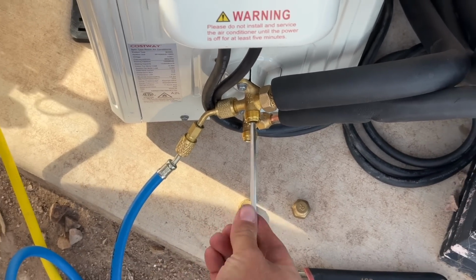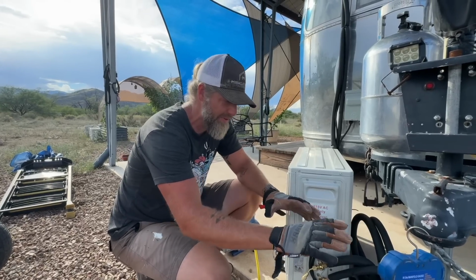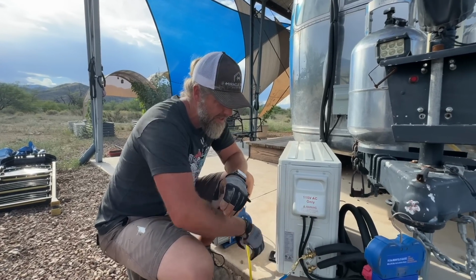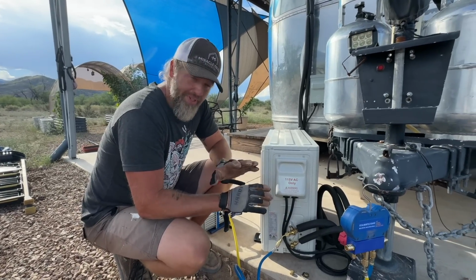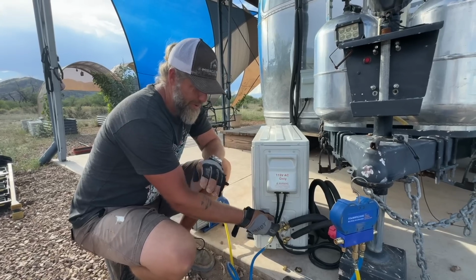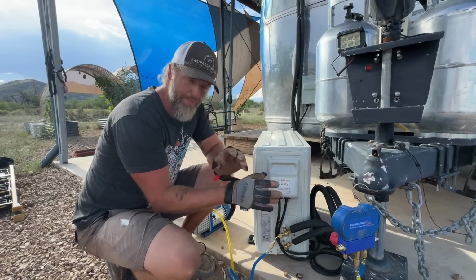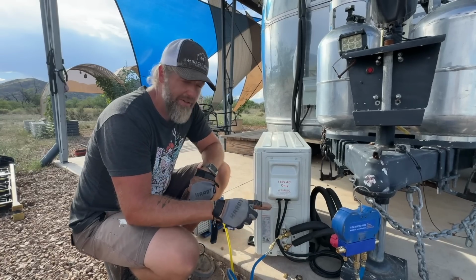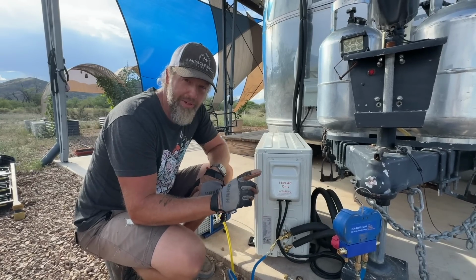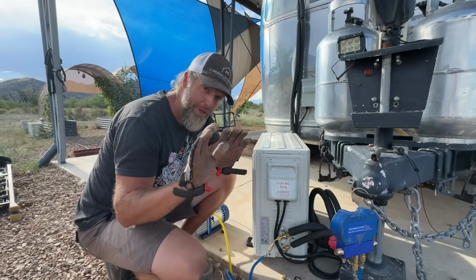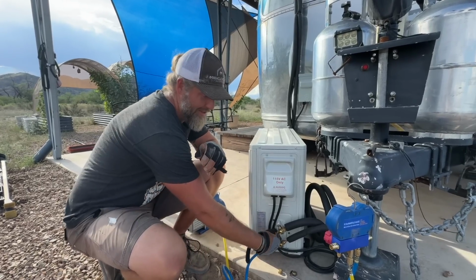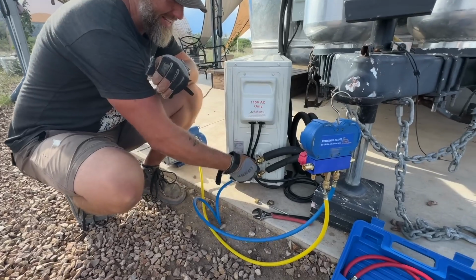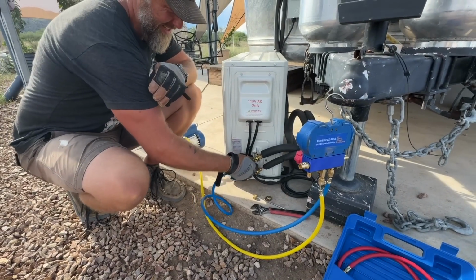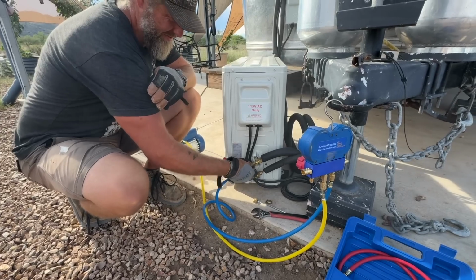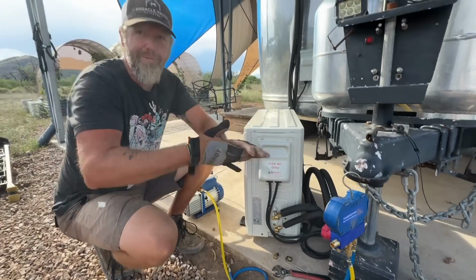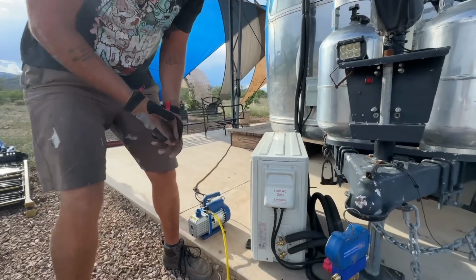Now here's the last thing: we have to disconnect the whole manifold off of this service port. There's refrigerant in there, and since this is a Schrader valve, it's going to want to spray refrigerant when you do this. Your instinct will be to stop when you hear it - don't, just keep going, wear gloves, and do it as fast as you can. Ready? Here we go. Woo, okay, that's why you wear gloves.